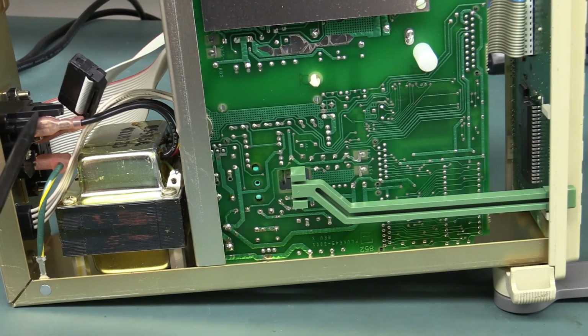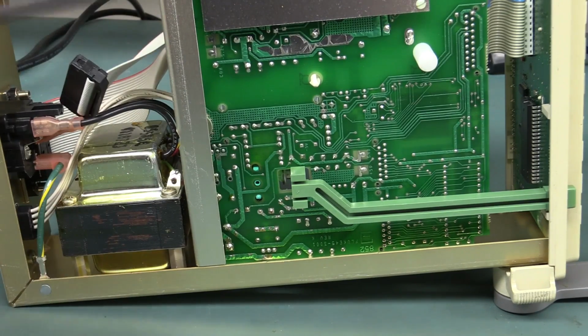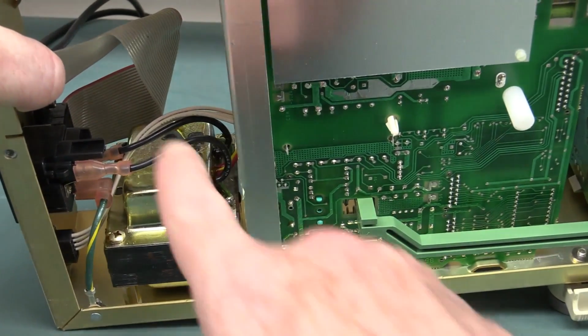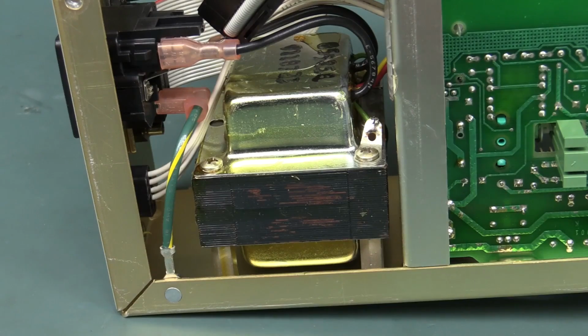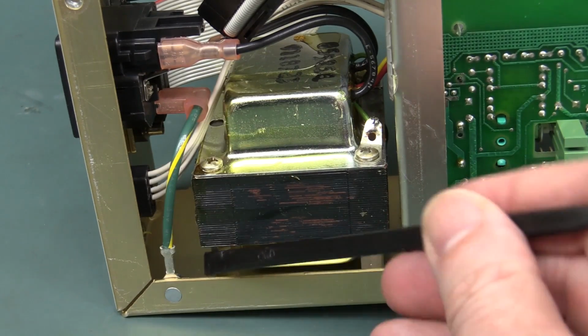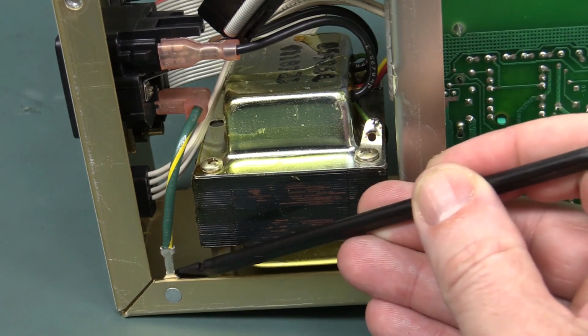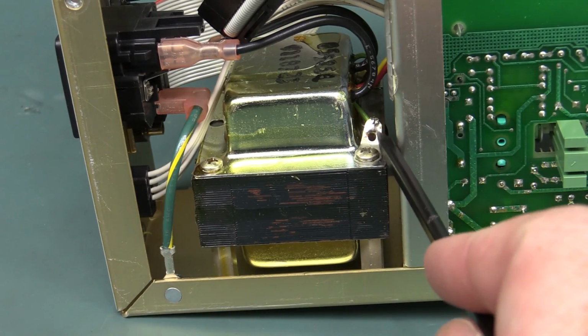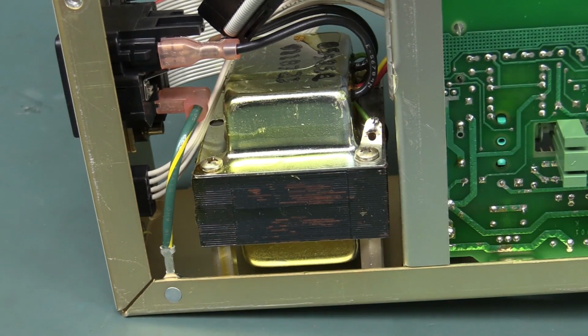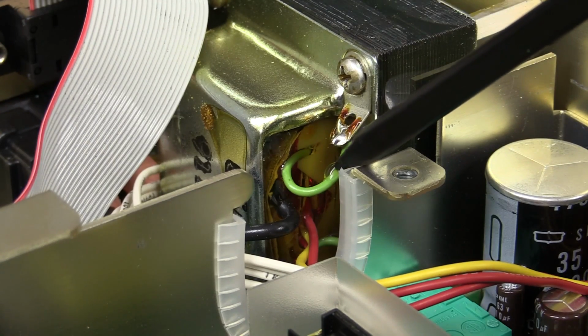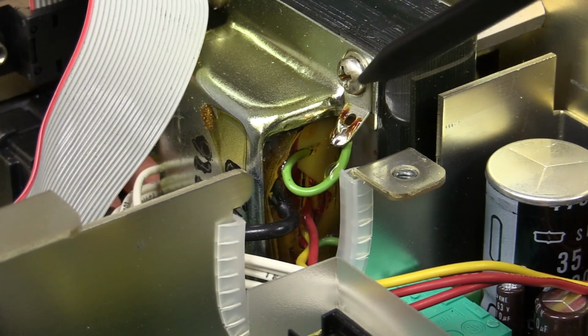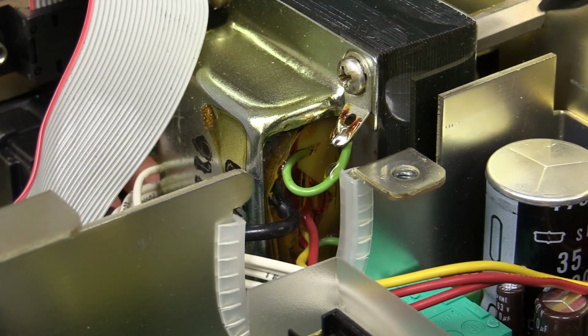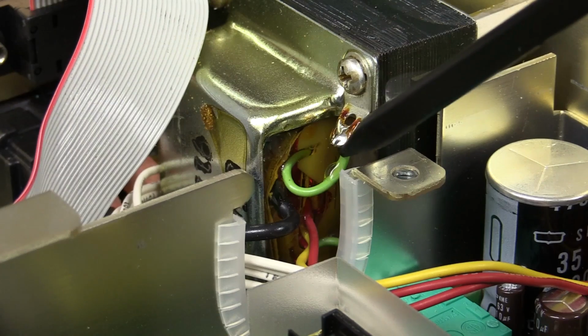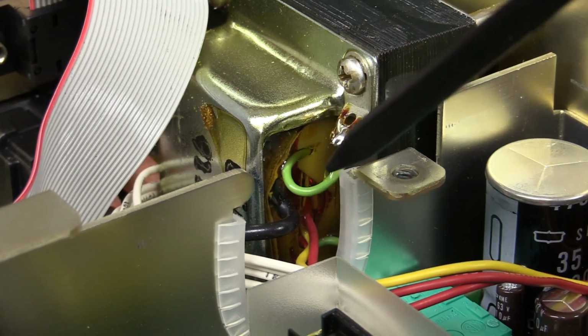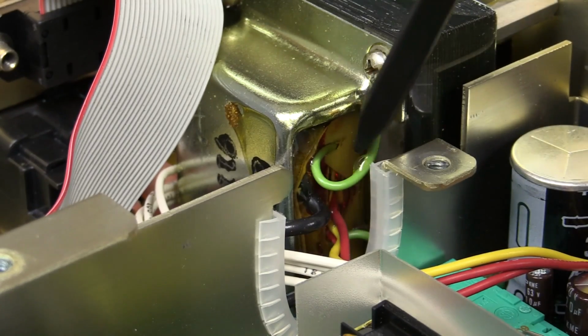If you have a look over here, here's our IEC mains input connector here. It's going straight into the transformer. Both wires there we go, boom, in like Flynn. And they've done the earth connection properly. You'll see that going down there. Yes, they've got a shake-proof washer down on there, but what's interesting is another earth connection here and on the other side. I'll give you a better view of this. Check it out, see? They've got another, well, it's an earth wire because it's connected to the frame of the transformer, which is connected through to the chassis, of course, which is connected to mains earth. So it's mains earth, it's going into the transformer. And as I said, there's another green wire right down there, if you can see it.